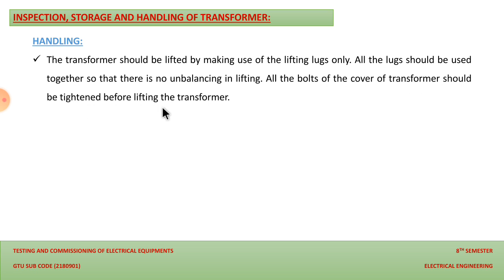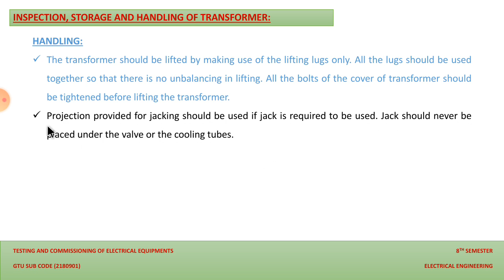And projections are provided for jacking, which means if we need to lift it to a certain height, then proper jacking should be applied, and the jack should never be placed under the valve or cooling tube. So yes, if we need to use jacks, we should protect our transformer from damage, because this is the soft portion of the transformer, where the valve or cooling tubes are there. So we have to lift our transformer from some other edges where these two are not present.